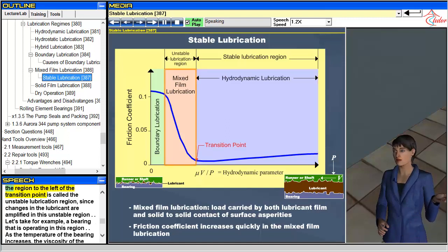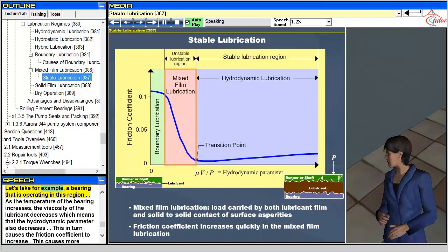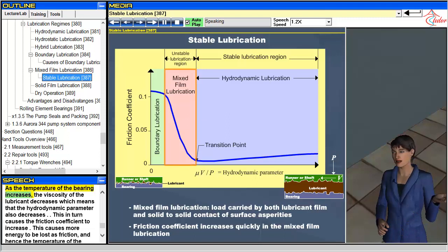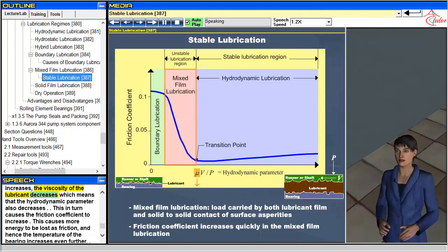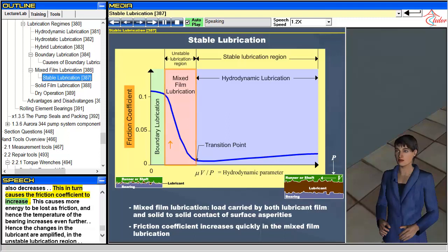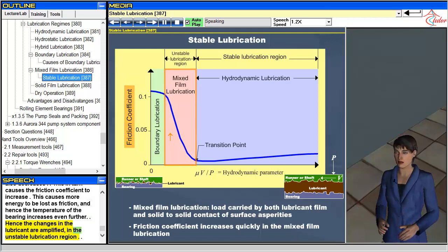On the other hand, the region to the left of the transition point is called the unstable lubrication region, since changes in the lubricant are amplified. For a bearing operating in this region, as temperature increases, lubricant viscosity decreases, causing the hydrodynamic parameter to decrease as well. This in turn causes the friction coefficient to increase, resulting in more energy lost as friction and further temperature rise — hence changes are amplified in the unstable region.